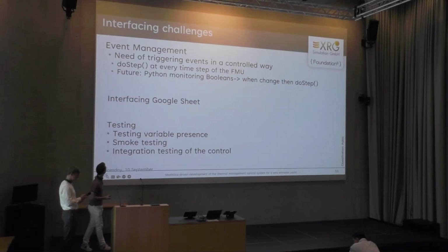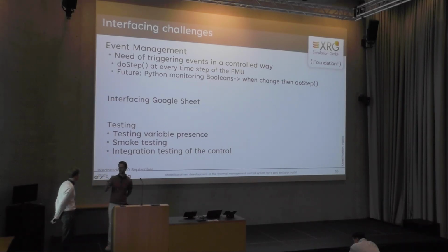Then some of the other things we did is to make sure that XRG is using the same variables that in the future the PLC supplier will be using. We had a Google Sheet with all the I/O values, and we actually checked that against our Python code and against the simulation with an automated test. So if anyone made a typo, we would know pretty much immediately. We are also testing if variables are present. We're also testing, if we send absurd inputs into the simulation, will the simulation break? So that we know they're mapped to something.